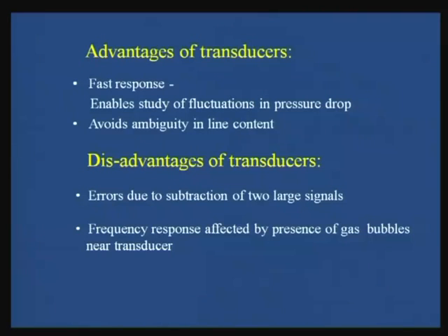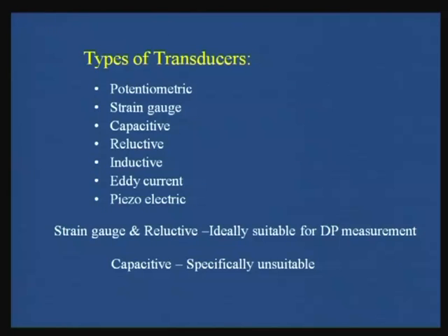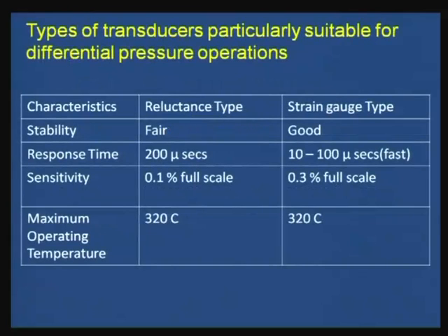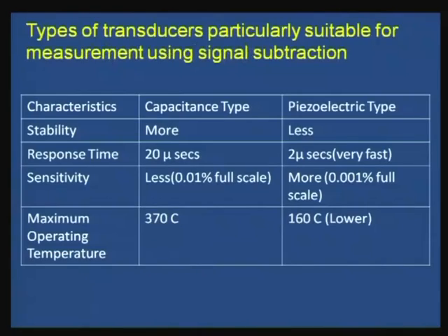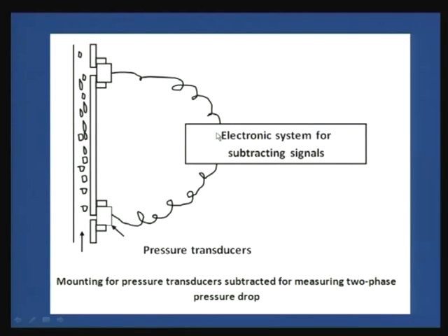Okay. So, therefore, to minimize the disadvantages of wall mounted pressure transducers, what have people adopted? They have adopted differential pressure transducers. Okay. What are these differential pressure transducers? More or less there are tapping lines. If I show you here, what happens? There is a tapping line from here, there is a tapping line from here, they enter into a box, and there is a diaphragm in the box. So, therefore, the pressure here and the pressure here are different.